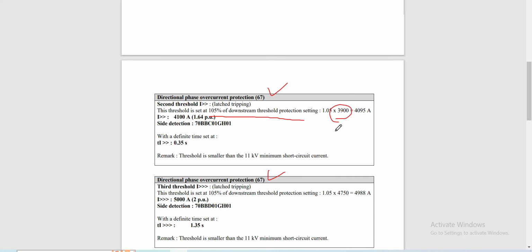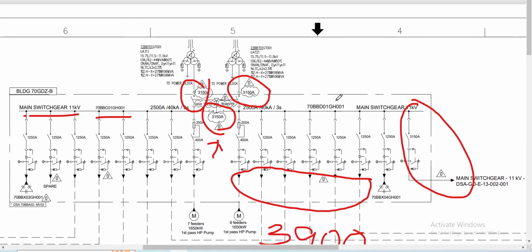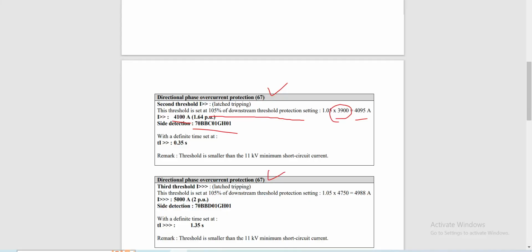Multiplying 105% by 3,900, we have 4,095 ampere, so our second threshold pickup current is set at 4,100 ampere, or 1.64 per unit. The side detection is at building B on this side from here, from this building. Then this is set at 0.35 seconds. This is on the first direction.